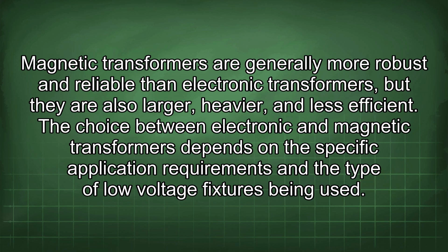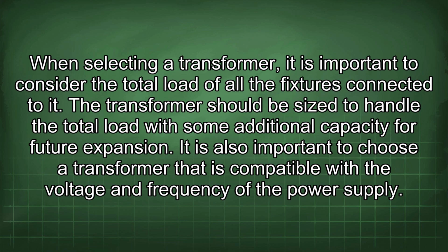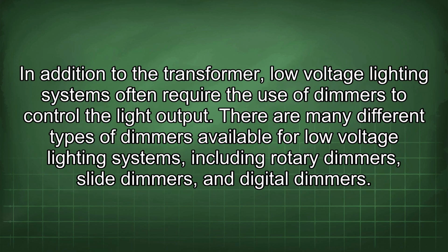being used. When selecting a transformer, it is important to consider the total load of all the fixtures connected to it. A transformer should be sized to handle the total load with some additional capacity for future expansion. It is also important to choose a transformer that is compatible with the voltage and frequency of the power supply. In addition to the transformer, low-voltage lighting systems often require the use of dimmers to control the light output.